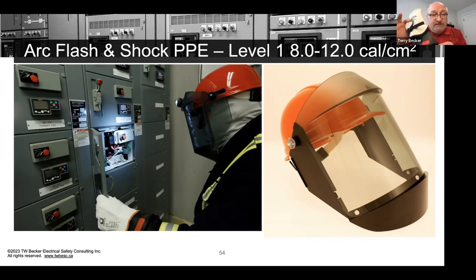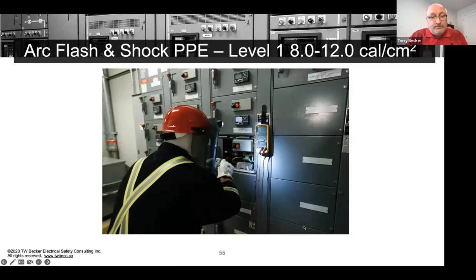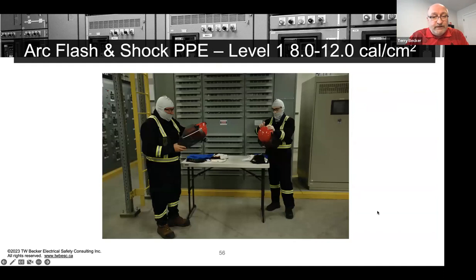Vendors have tested these. This class zero could be good up to 40 calories, and that's before the rubber would melt. So it's significant protection. And I recommend, if you're not exposed to shock and only arc flash, you wear the right class of rubber insulating gloves. So just another example picture: a worker doing diagnostics on a motor control center starter bucket, a couple of workers pre-use inspecting and donning the PPE. Yes, that's actually me if you look close. So you've got to pre-use inspect all of it, don it, and put it on.